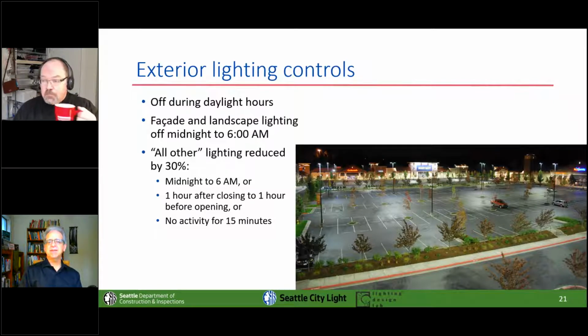Facade lighting and landscape lighting shut off completely between midnight and 6. For everything else in exterior lighting, which should include this parking lot, you've got to dim the lights either between midnight and 6, or if you're a tavern, maybe from an hour after closing to an hour before opening, with occupancy sensors that dim the lights after 15 minutes, or with a time clock function. And if you're going to dim them 30%, hey, why not 50?